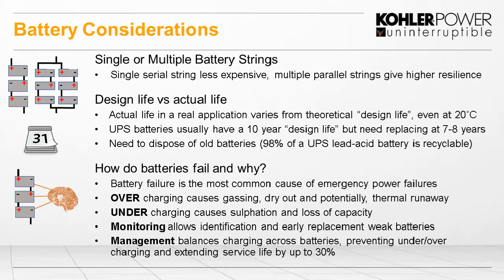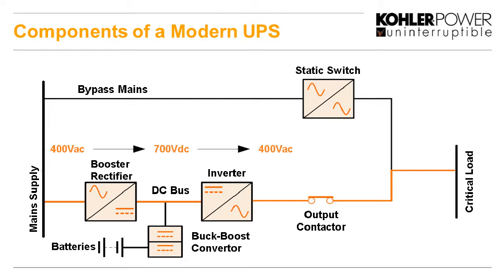So going on to the actual UPS itself and looking at components of a modern UPS, we have in front of us here a typical UPS diagram, where we have a main supply here on the left, feeding into the booster rectifier at the bottom, into the DC bus. So that converts the AC mains into DC, which is one conversion. And then the inverter converts that DC back into AC, which feeds out to the critical load there on the right. Now, those two conversions are why a lot of modern UPSs are called double conversion or dual conversion.